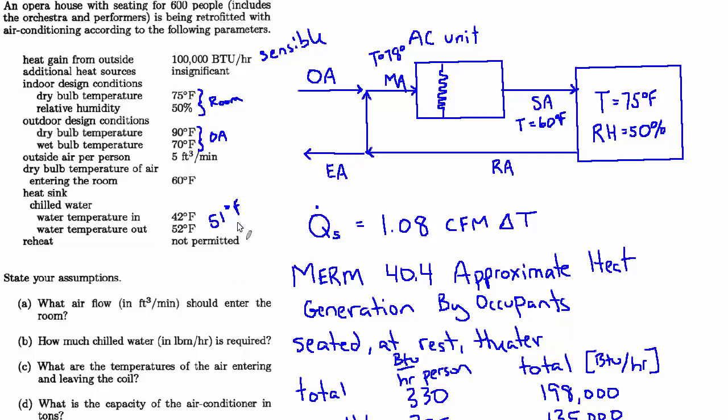So I think 51 is pessimistic. That's assuming that the coil is going to be almost as warm as the chill water supply temperature. It's definitely a conservative approach. You could say it's 51. But I would argue that it's probably much closer to the chill water supply temperature, 42.